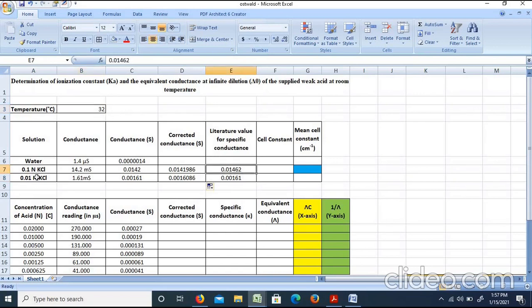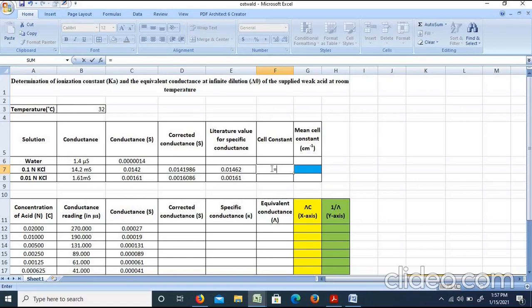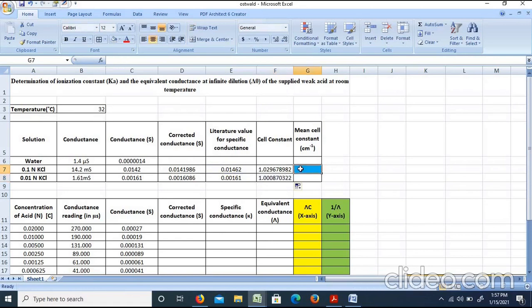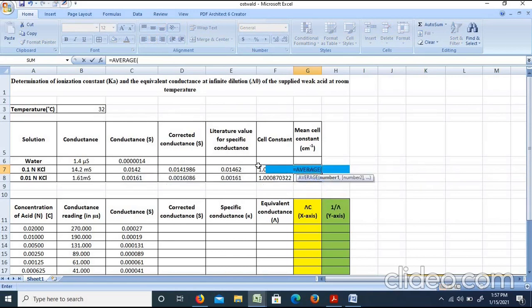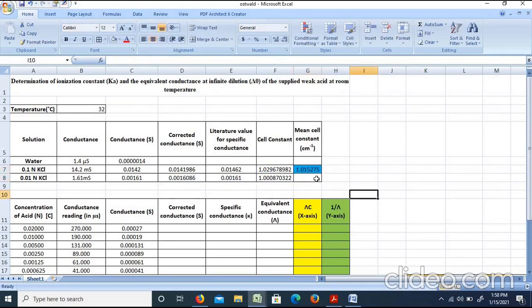At a temperature of 32 degrees centigrade, for 0.1 normal KCl and 0.01 normal KCl, the specific conductance is the literature standard value. The cell constant equals specific conductance divided by the corresponding corrected conductance. We calculate the cell constant for each KCl concentration and take their mean. The mean cell constant obtained is 1.015275 cm inverse.